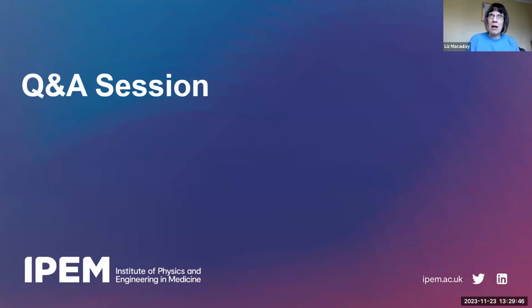so this MPACE will actually then look at, well, what is in your commissioning report? Is there everything that we would expect? Does it look at the uncertainties of measurement? Does it address any risk in bringing that commissioned piece of equipment into clinical use? So that side of things is covered by MPACE, which wouldn't be covered in a quality management system.